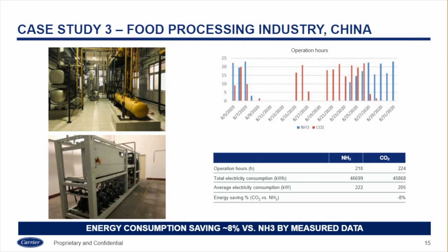The next case is another case study for the food processing industry. This is one facility in China. We are comparing the ammonia system and the CO2 transcritical system. The cooling capacity of the two units is pretty similar, and we counted about 1 month of operation for both systems. You can see the chart here. In August, the hottest season in China, these two facilities are running in sequence because they have different duty.